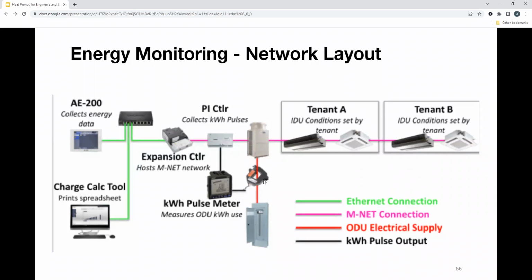So right here, you'd add in a current transducer. This does need to be revenue graded, about 1% down to 10% of the rated size associated with that. And this is connected to a kilowatt pulse meter, right? That basically requires a 24-volt battery supply. And this is basically calculating how many kilowatts are used by this outdoor unit.